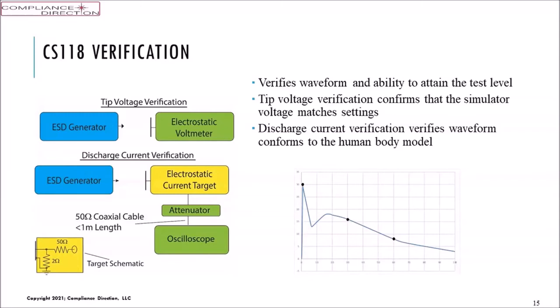So we need to verify the waveform at the various currents that are doing a direct or contact discharge. And we see that the waveform follows the shape that we have over there with some measurement points for the current to say that's what we have at those points. The standard is pretty specific on doing that.